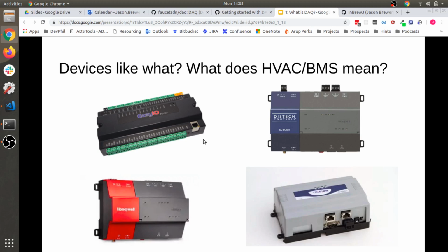These boxes can communicate via sometimes IP, a growing number of devices communicate over IP these days, and they communicate with each other through other protocols like BACnet and Modbus and LON and all this other stuff. But for the sake of this, just think of these boxes as sort of generic I/O controllers. So you can plug in a sensor to one of these inputs, and you can plug in an actuator, motor or something into another output, and you can connect the two together.